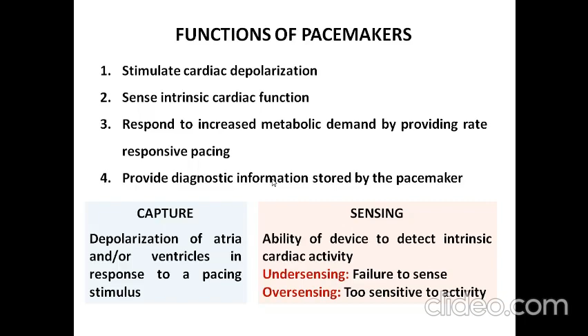And regarding the electrical stimulation of cardiac tissues, we already know that cardiac activity must be properly supported by a pacemaker for normal function of the heart. So an artificial electrical stimulus excites cardiac tissues by the creation of an electrical field at the interface of the stimulating electrodes and the myocardium. The electrical field should be strong enough and last long enough to initiate action potentials in the cells at the electrode and tissue interface. So we need a minimum voltage per centimeter to trigger a self-propagating wave of depolarization. Likewise, we require a minimum current per centimeter square to trigger the self-propagating wave of depolarization of heart activity.